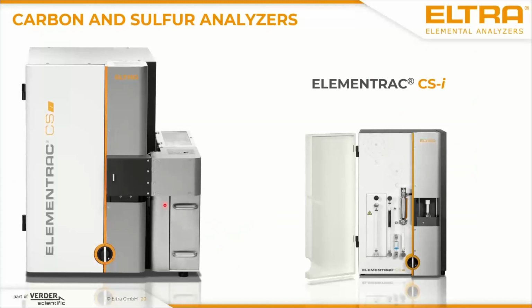Okay, next are the carbon and sulfur analyzers after the ONH analyzers. Here is a picture of our ELEMENTRAC CS-i. On the left side is the CSI as it is. On the right side, it's the same instrument, the picture is a little bit bigger here. The instruments are actually the same size, but here you see the autoloader attached to the instrument. Customers with high throughput can select between a 36 or 130 positions autoloader from ELTRA, which will automatically load the analyzer and distribute the samples there. Quite convenient and a lot of time saving.